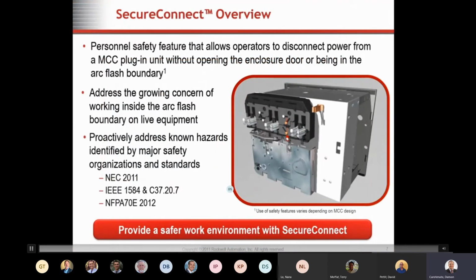So how this is done. What this does is address all the governing bodies, the NEC, NFPA 70, IEEE. They've recognized this arc flash boundary in live equipment. They've done all the studies on that. They've talked about the calorie counts. So they do understand the exposure that personnel are getting to dangerous voltages, and they are understanding the opportunities for someone to get hurt or an incident to occur that would cause a catastrophic event to not just the person, but the equipment as well. So they are proactively addressing these hazards. Like I said, they're trying to take some of the medium voltage criteria and plug it into the arc shield MCC, and now this is another way to help isolate the unit itself from any type of live power within the MCC bucket itself.